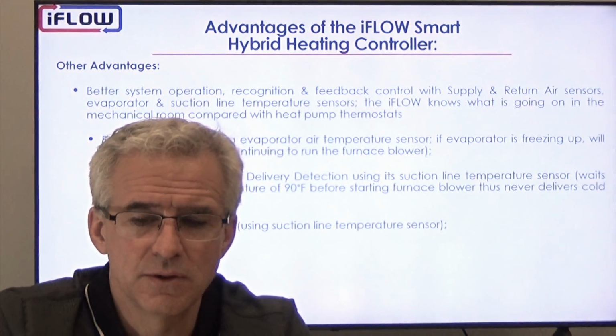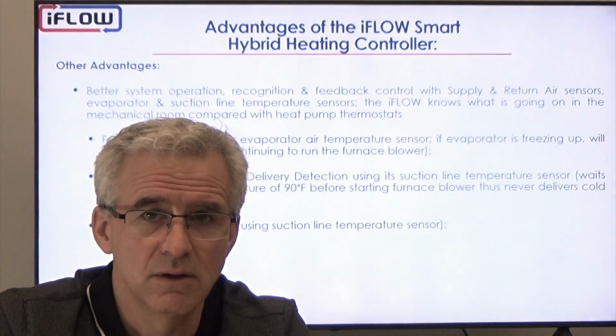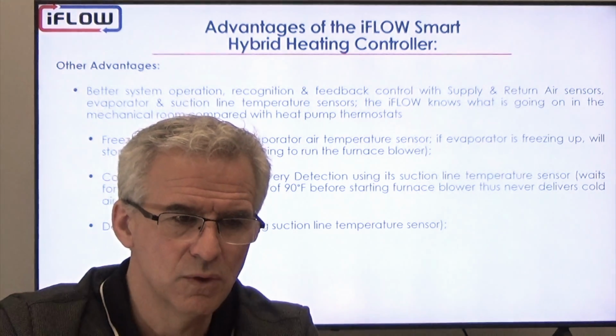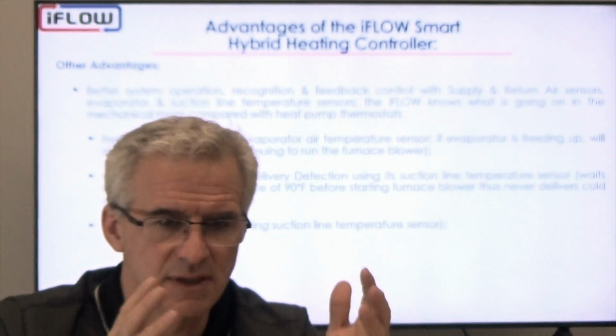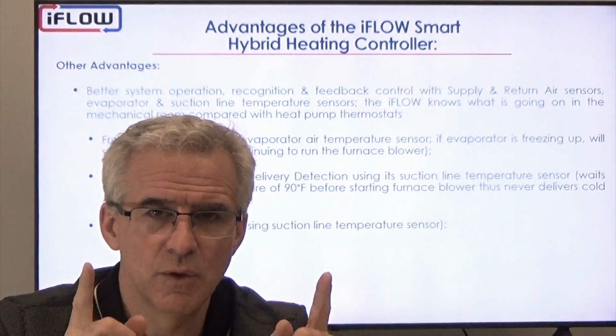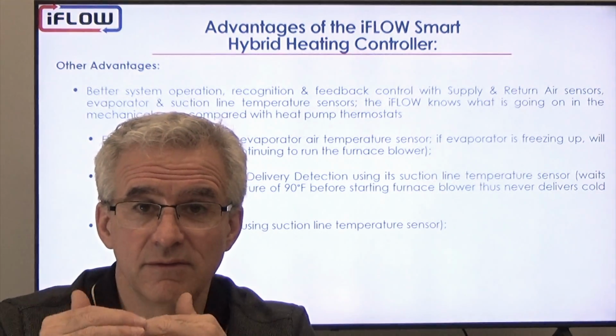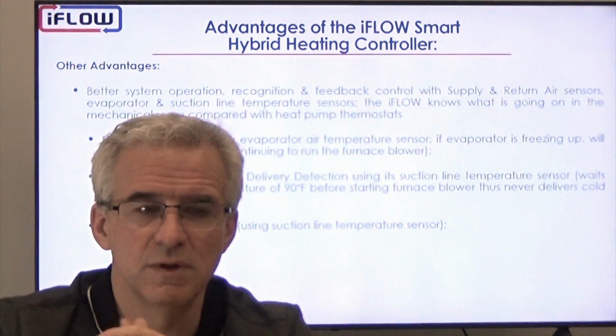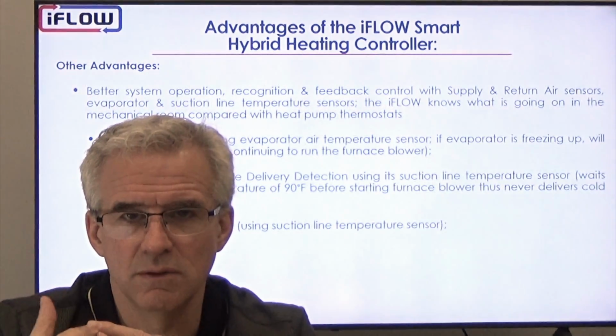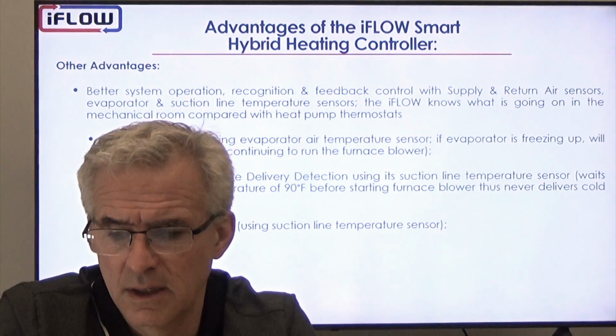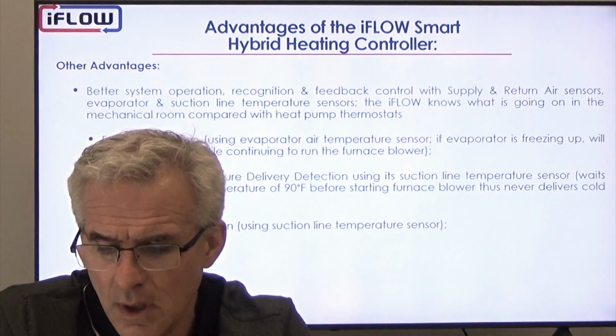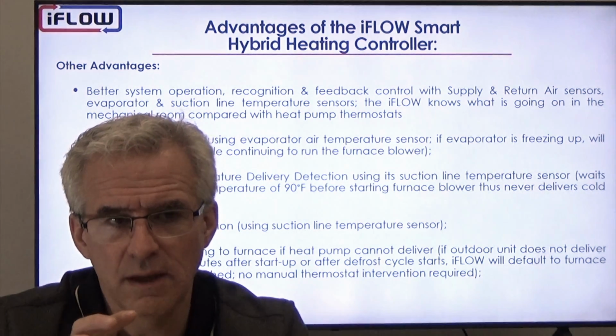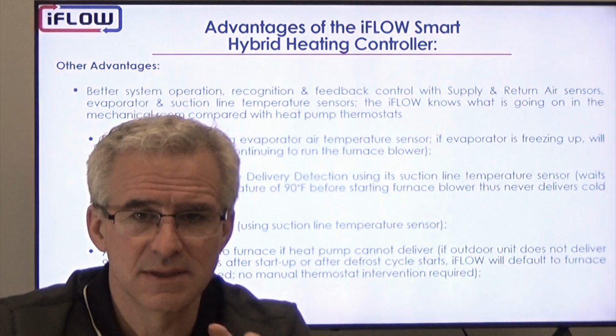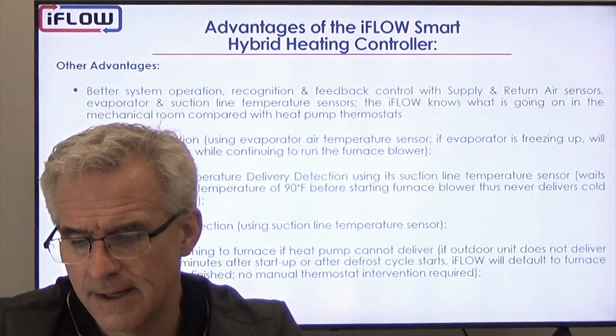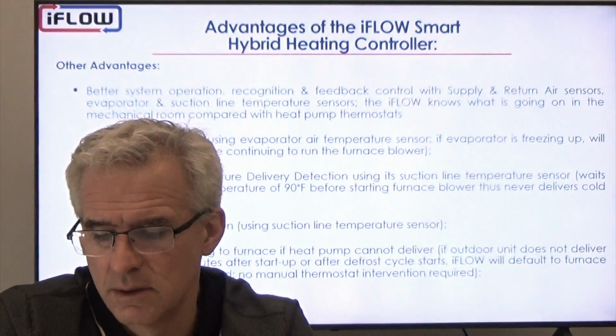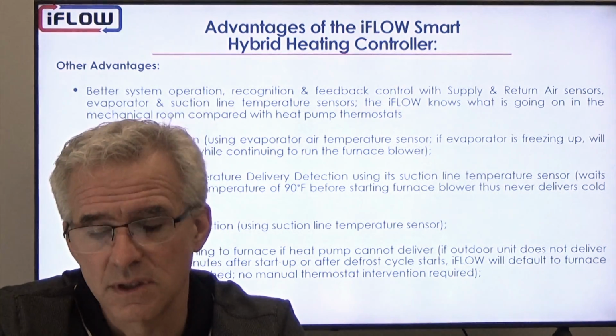We also use that suction line temperature to monitor the defrost cycle on the heat pump. So if the heat pump goes into its defrost mode, we're looking at a cycle time of maybe 5, 6, 10, 12 minutes. If within 20 minutes we have not received heat in the way of above 90 degrees Fahrenheit, then we will also assume that the heat pump is having a problem in defrost mode, and we will switch to the gas backup. So a couple of functions that suction line temperature is providing. But all to say, with those sensors, we are looking at the mechanical systems themselves and assessing whether they're working properly or not, and then adjusting which one we're calling on depending on the feedback of those sensors.